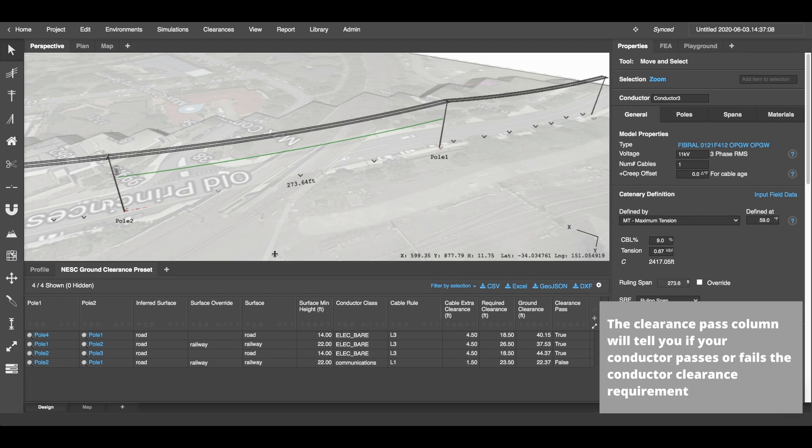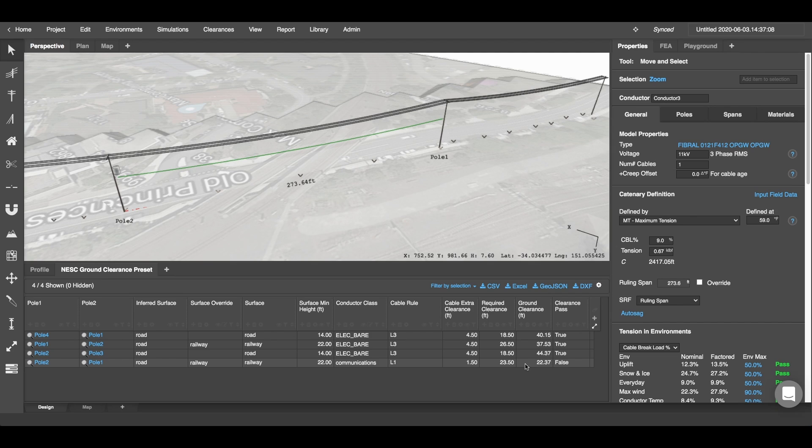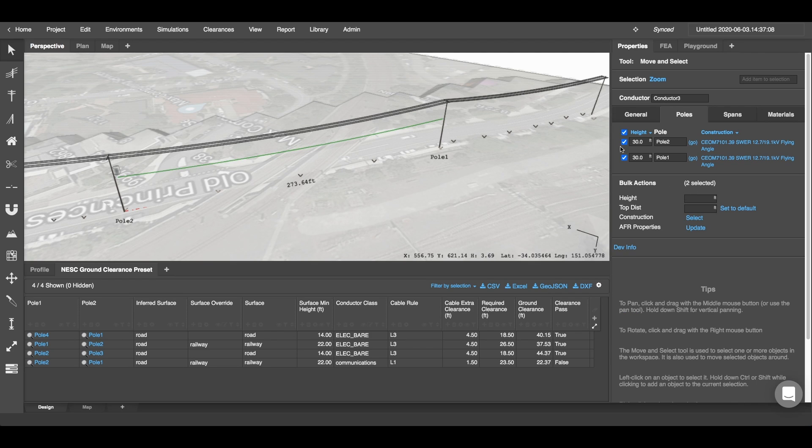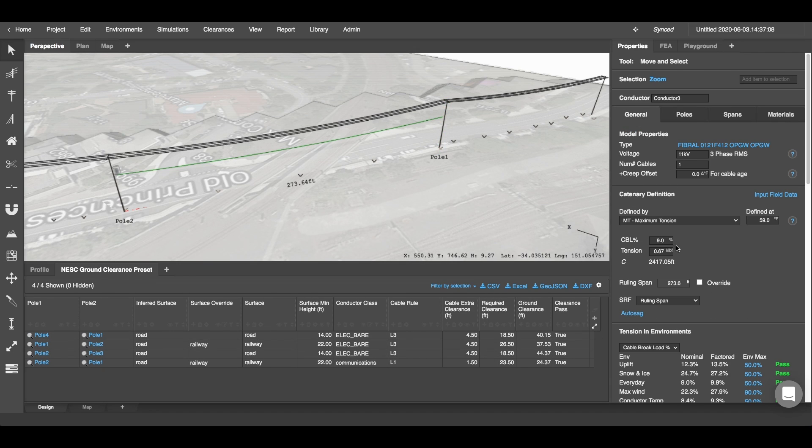Pole 1 and Pole 2, our communication cable here, is actually failing our required clearance. We can see here by the comparison that it's failing by only a few inches. So what we can do is we can select the conductor and probably increase the attachment height both sides to maybe 32 feet and that will make this pass. You can also do things such as increasing the tension of your cable.